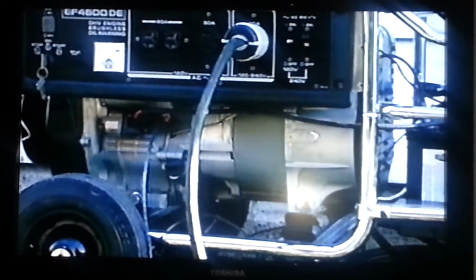To test the automatic power transfer, move the auto off test switch to the auto position. Then turn off the double pole breaker in the service entrance panel. The generator should start, and after about 10 seconds, power should be restored. Turn the double pole breaker in the service entrance panel back on, and the automatic transfer switch will turn the generator off. To leave your ATS system in the ready position, perform the following.